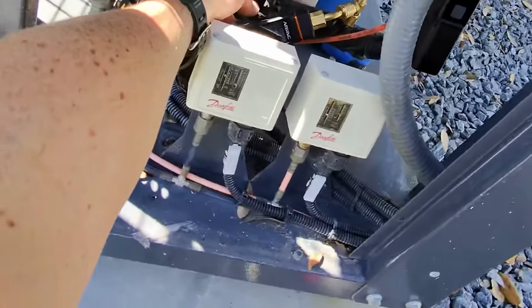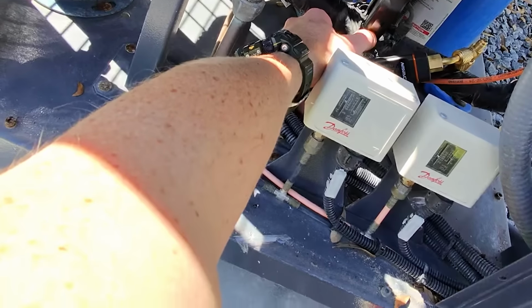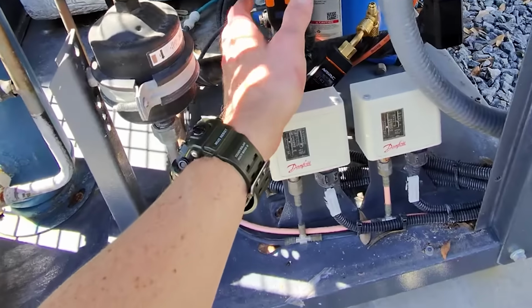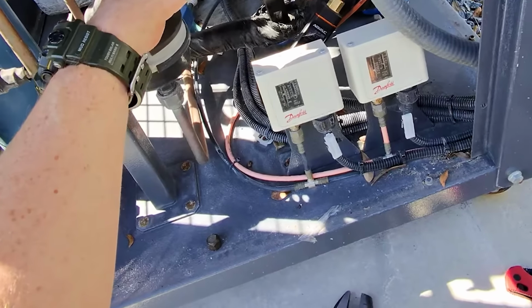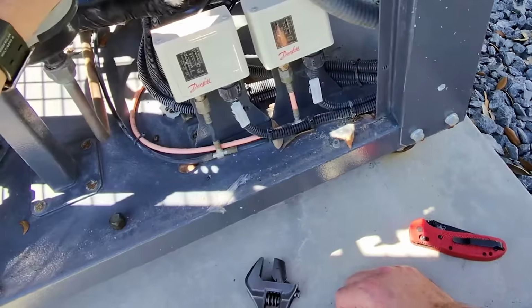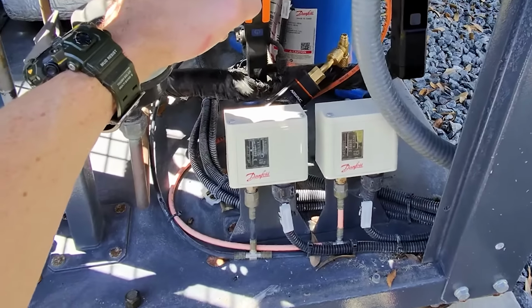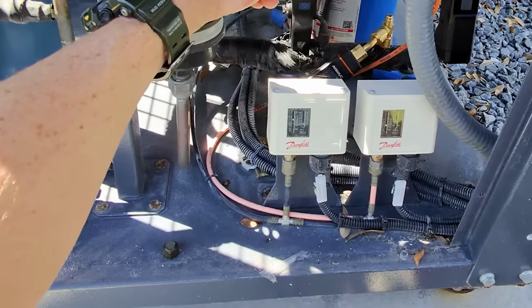218 psi on the suction, and look at that. My suction line is actually 100.7 degrees. It is roasty toasty. And I haven't checked the temperature of the water in the tank, but it would make sense if refrigerant is flowing back from the tank that it'd be this hot. But the question is why. I want to let the compressor run for an extended period of time.